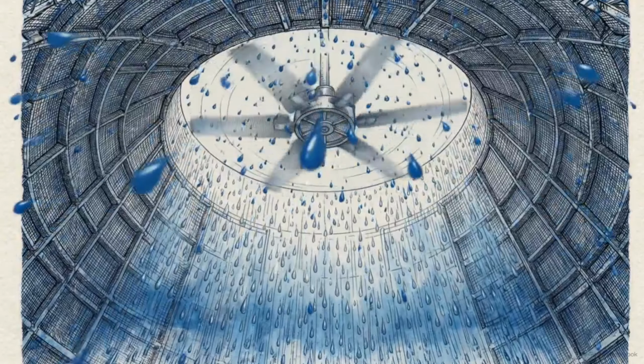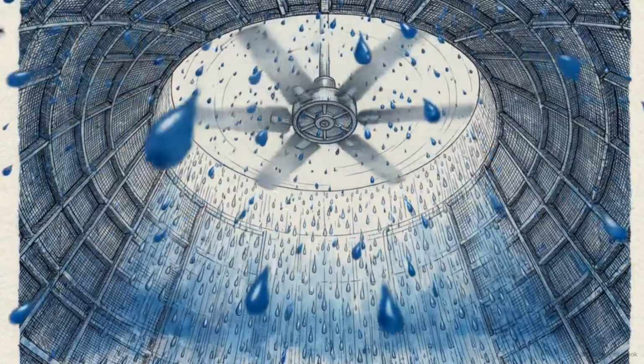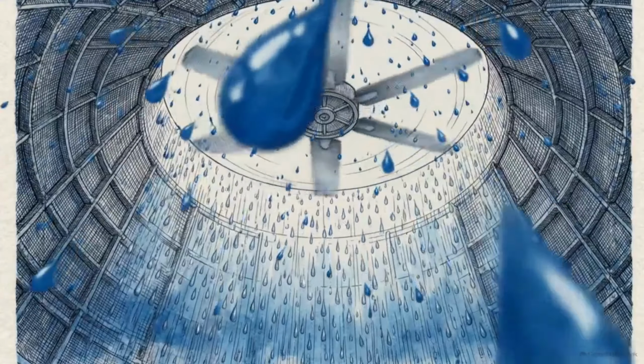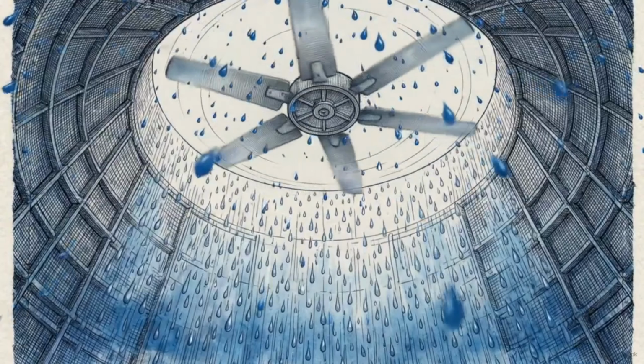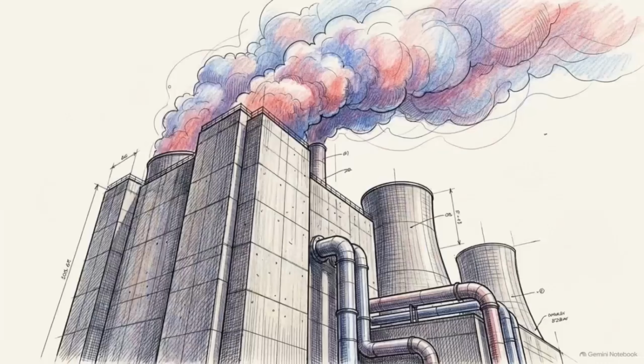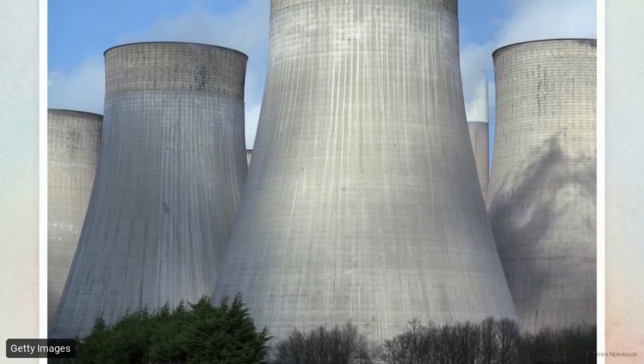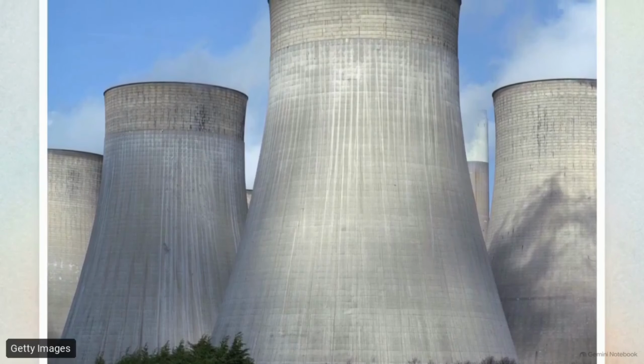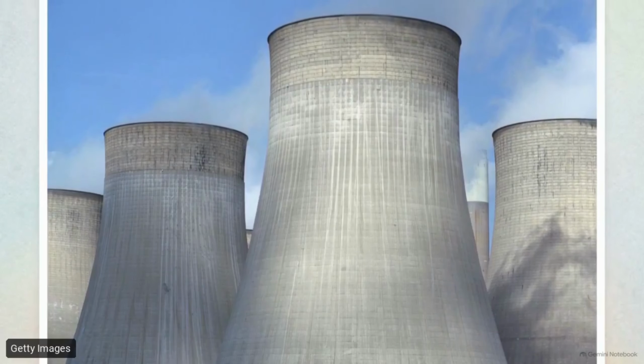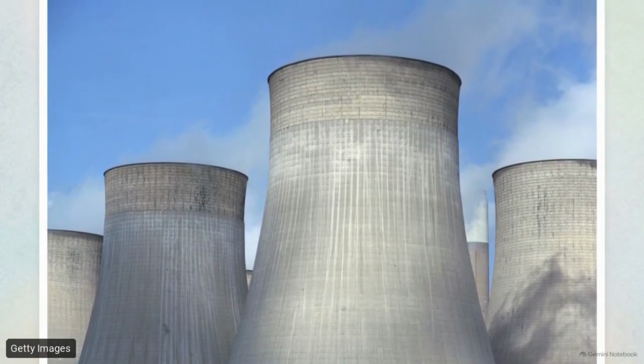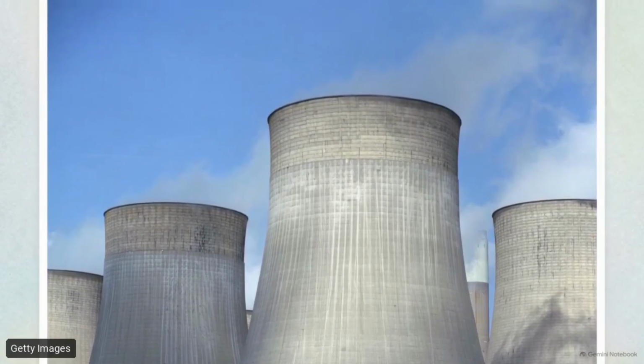Every internal mechanic of a cooling tower serves one singular purpose, acting as a massive surface area maximization machine, evaporating water as efficiently as possible. When thermal loads reach massive industrial scales, the physical architectures change entirely. In large power plants, engineers use natural draft towers. The hyperbolic shape of the concrete creates such a powerful updraft that mechanical fans aren't required.